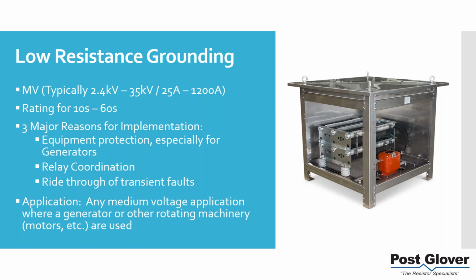And change that to, let's say, 400 amps. So you have a much smaller amount of current flowing, therefore energy flowing, and therefore the amount of damage is much less as well. Essentially, energy times time is roughly equivalent to the damage you're going to receive. So obviously, if you lower that amount of energy way down, then you're going to experience a lot less damage as well, relatively speaking.